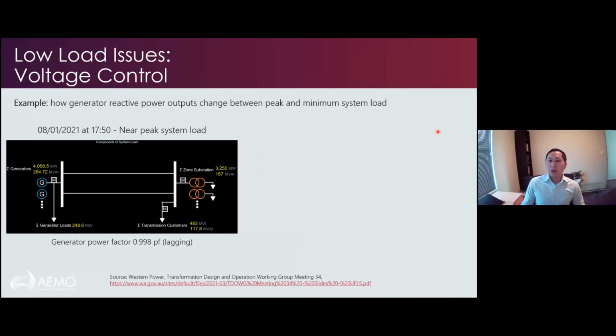So in terms of voltage control, the generator reactive power outputs, this is an example of how they've changed between the peak and the minimum load. So during peak load, this is a slide from Western Power from a T-Dog workshop recently, and we had a near system peak load of about 4,070 megawatts early this year, and you can see the generators are basically injecting 265 MVars of reactive power.